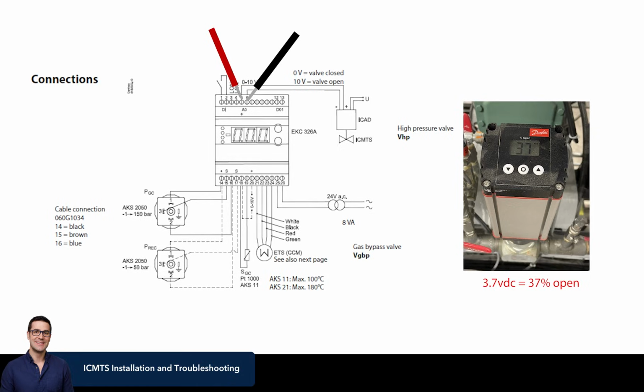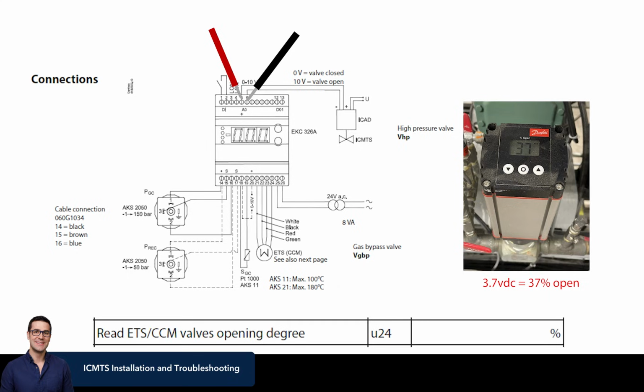So we want to make sure, A, that we're getting some type of voltage, and then B, we would move on to, again, those parameters in the EKC if that's where we're looking, or the service tool if it's the pack controller. But we can compare what opening degree the controller thinks the valve is at versus what voltage signal is going to the valve, and then move on to maybe manually opening the valve to see if it's moving at all.